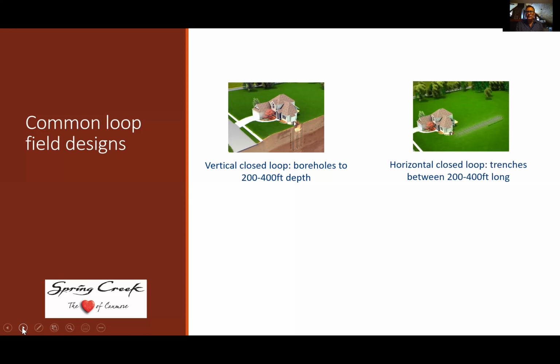The horizontal closed loop trenches - that's what I did at my house in Tamarack, in the rec center. That worked very well for me; I had the land for it. We dug a big hole 10 feet down, did our horizontal loops, filled it with 3 feet of fill on top, did another horizontal loop at 7 feet, then brought those pipes into the building. It was basically the cost of the machine plus the cost of the plastic loops. It was silty there so I didn't have to bed it in with sand - very efficient for me to do.